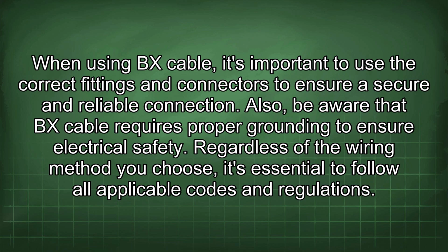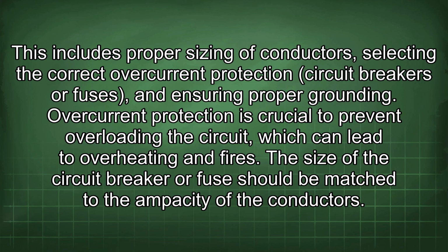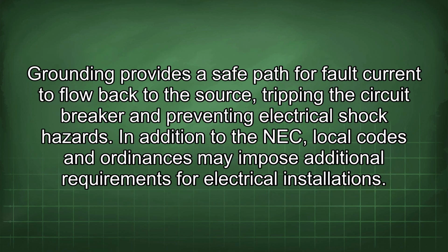Regardless of the wiring method you choose, it's essential to follow all applicable codes and regulations. This includes proper sizing of conductors, selecting the correct overcurrent protection circuit breakers or fuses, and ensuring proper grounding. Overcurrent protection is crucial to prevent overloading the circuit, which can lead to overheating and fires. The size of the circuit breaker or fuse should be matched to the ampacity of the conductors.